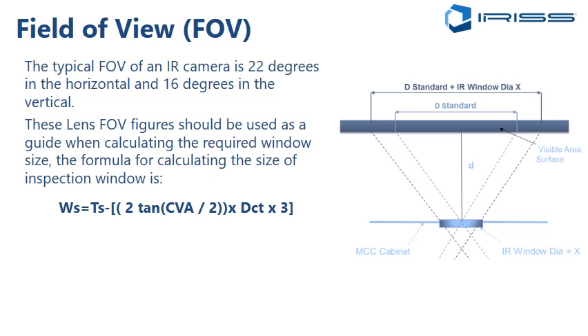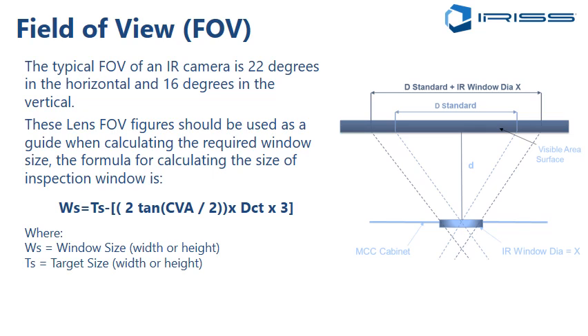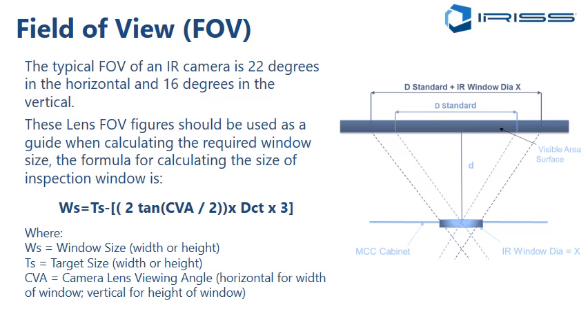The formula that we have here is WS equals TS minus 2 times the tan of the CVA divided by 2, times DCT, times 3. Which doesn't mean a lot, but basically WS is window size, TS is target size, minus 2 times the tangent of half the camera viewing angle. So that's a tangent of 11 degrees because we're looking at 22 degrees here. If you're doing it in the vertical, it will be 16 degrees, or 8. DCT is distance from cover to target.